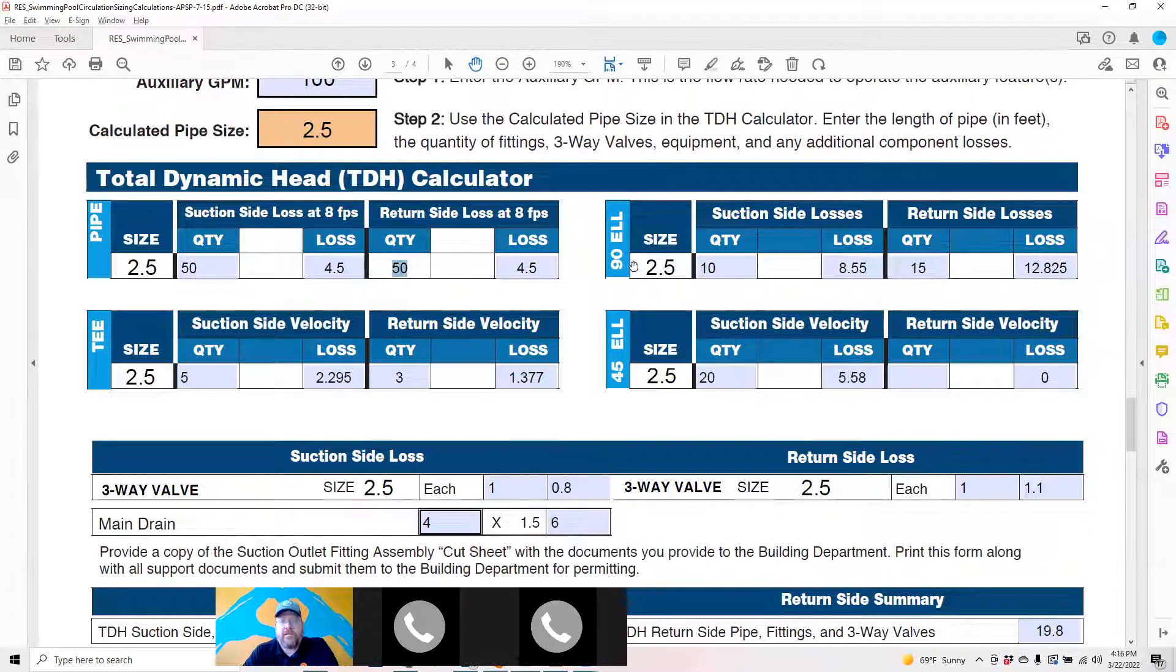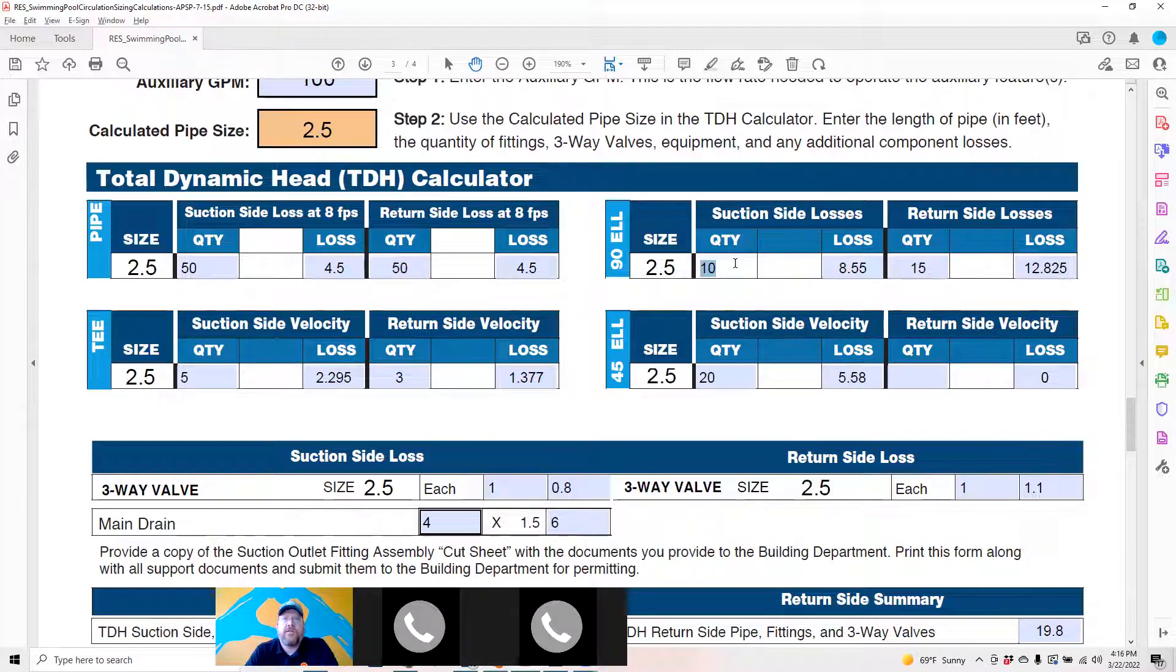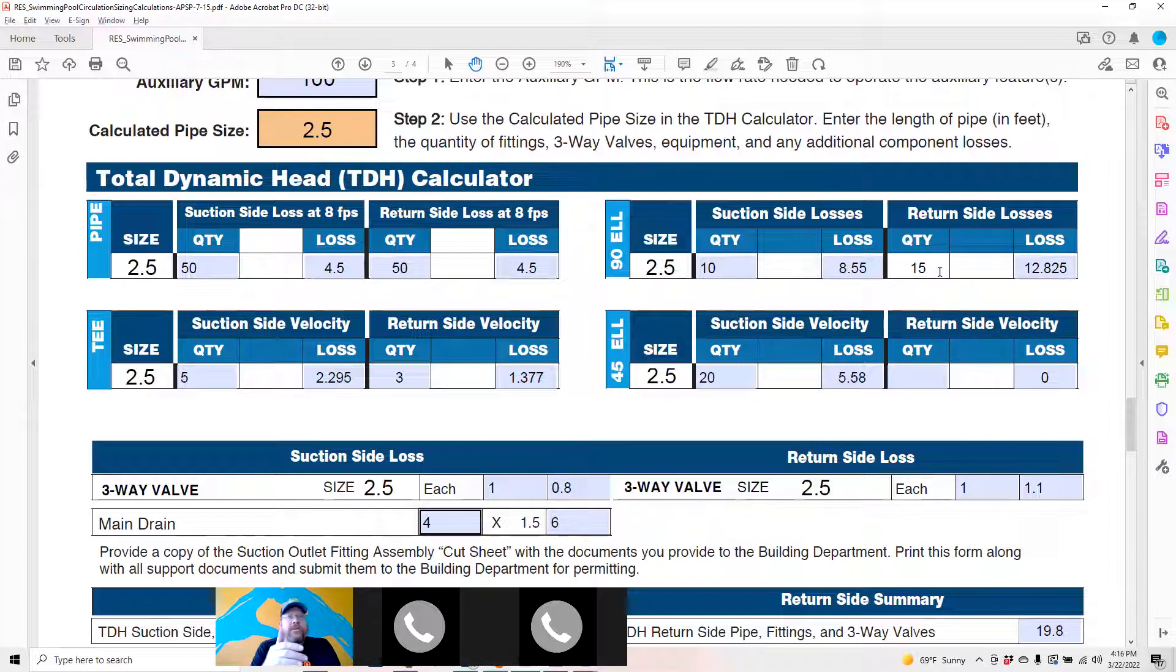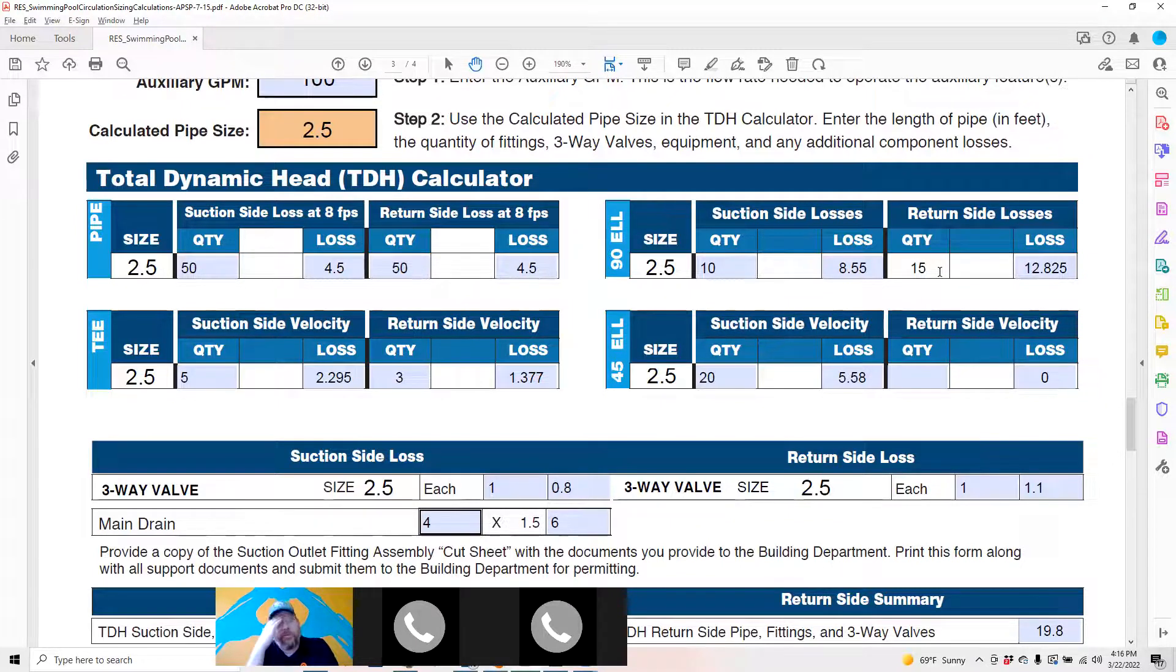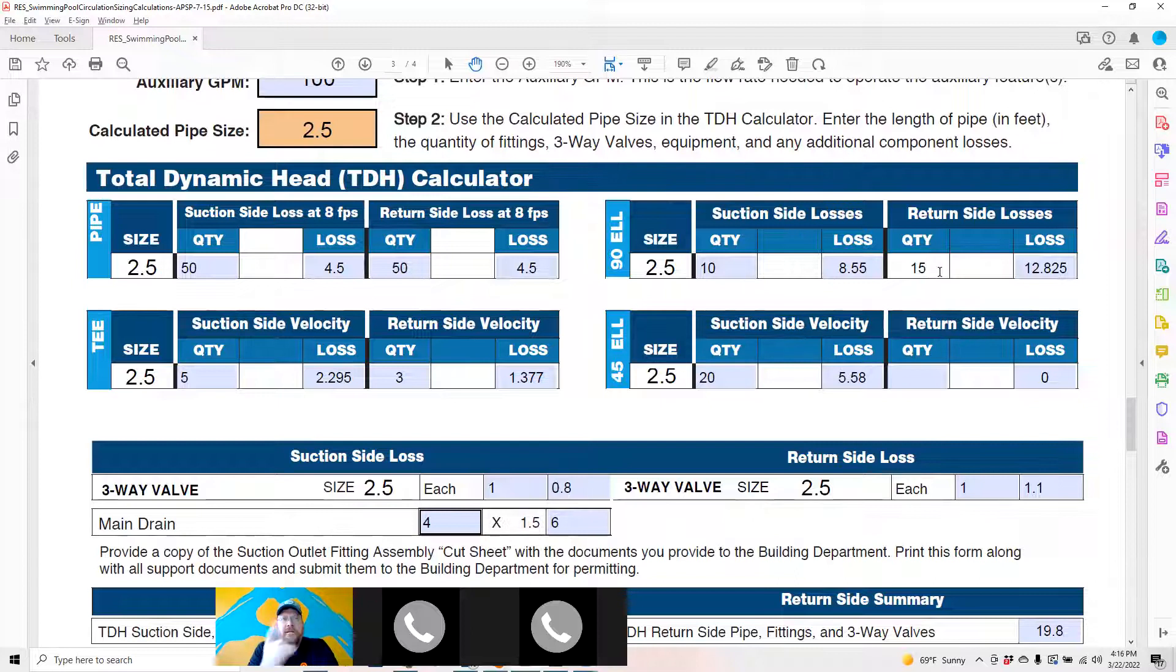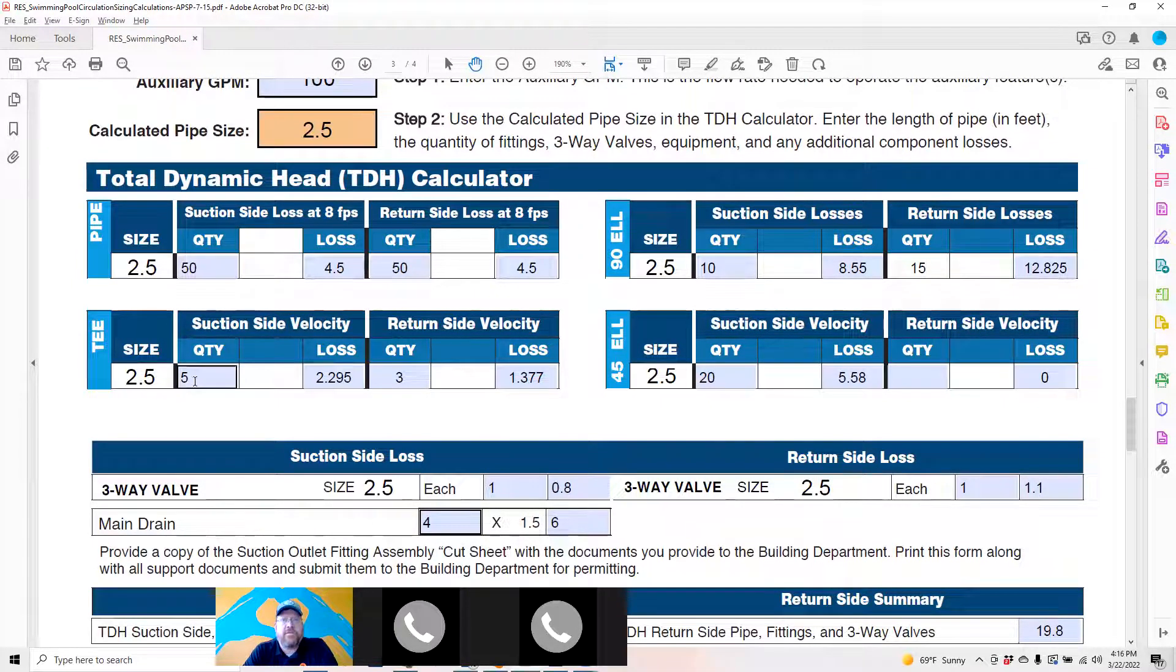The next is the number of elbows. The suction side is the number of elbows in front of the pump intake. Return side, there's 15 over here because it's all the elbows on the equipment pad from the discharge side of the pump—elbow over to the filter, from the filter elbowed over to the sanitizer, from the sanitizer over to the heater, heater to the manifold, and any other devices on there.